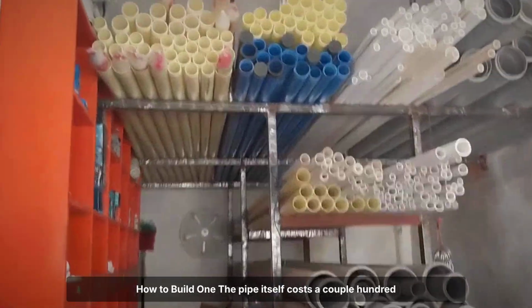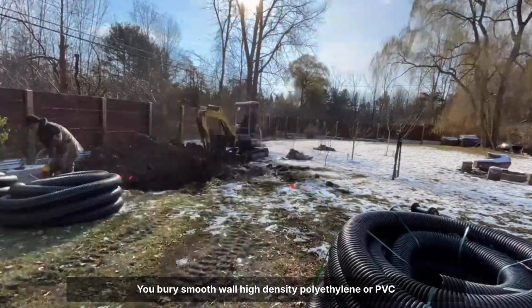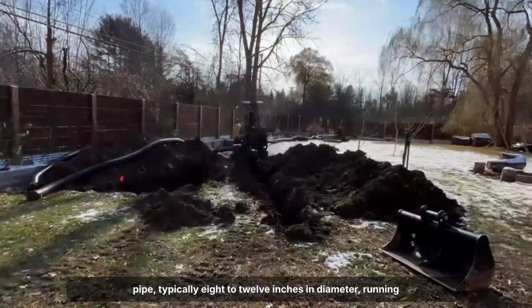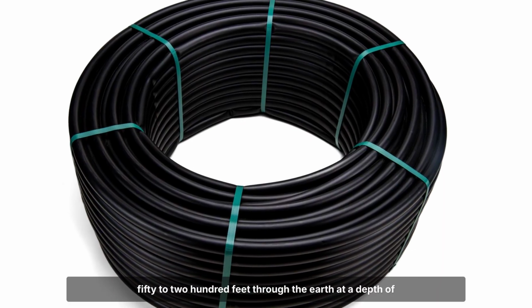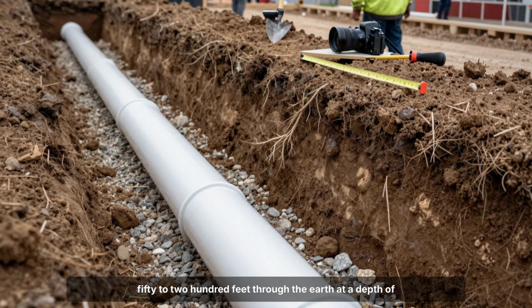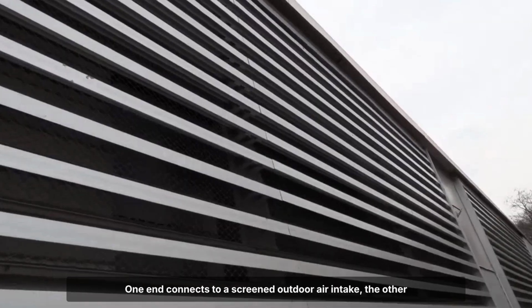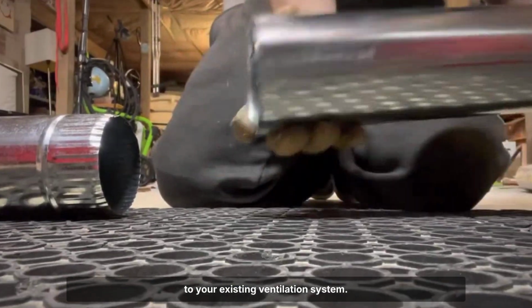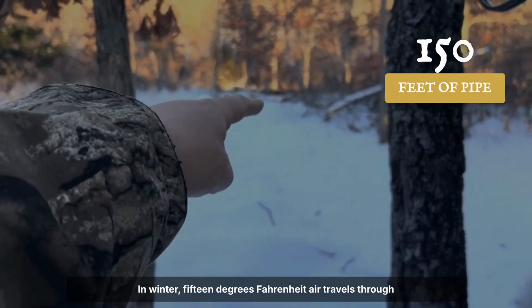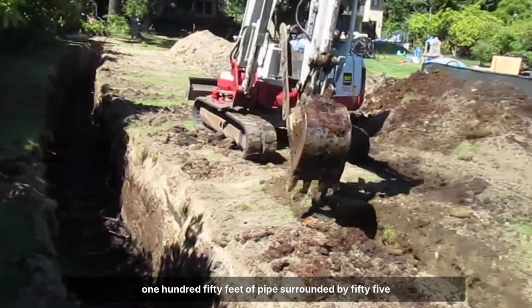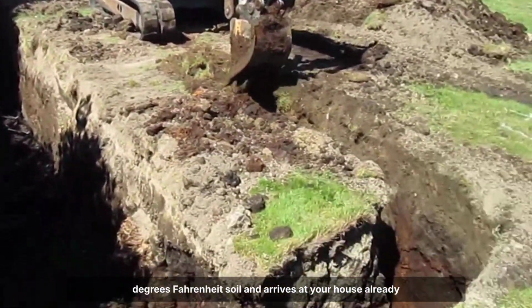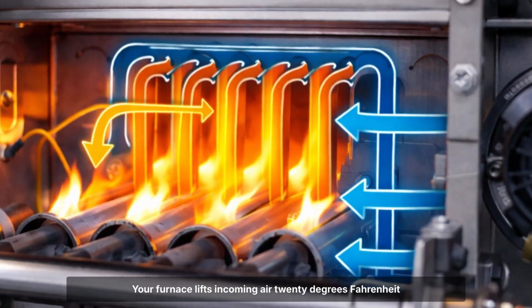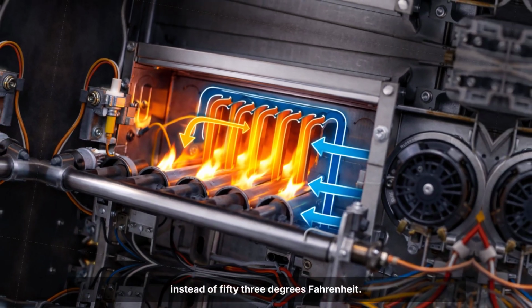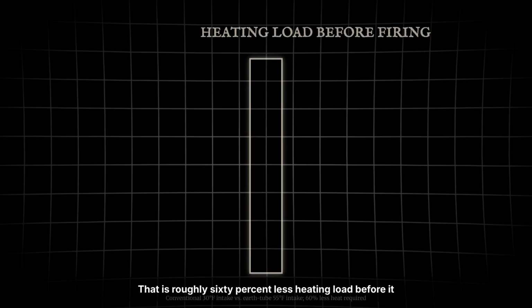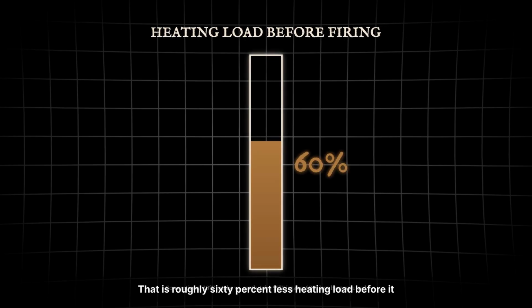How to build one. The pipe itself costs a couple hundred dollars. You bury smooth wall, high-density polyethylene or PVC pipe, typically 8 to 12 inches in diameter, running 50 to 200 feet through the earth at a depth of 6 to 10 feet. One end connects to a screened outdoor air intake, the other to your existing ventilation system. In winter, 15 degrees Fahrenheit air travels through 150 feet of pipe surrounded by 55 degrees Fahrenheit soil and arrives at your house already approaching 50 degrees Fahrenheit. Your furnace lifts incoming air 20 degrees Fahrenheit instead of 53 degrees Fahrenheit. That is roughly 60% less heating load before it fires once.